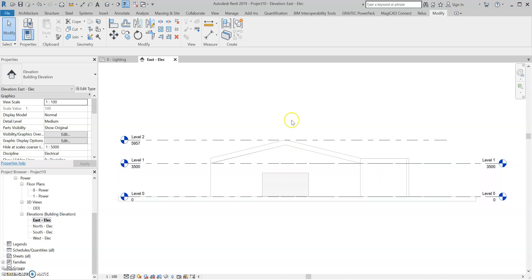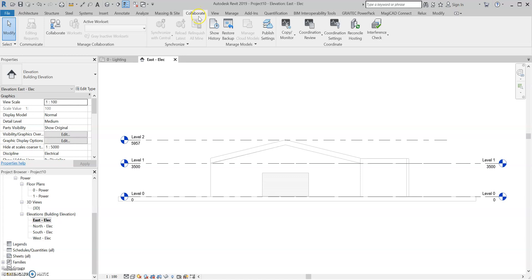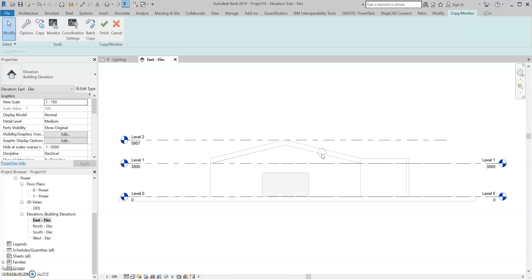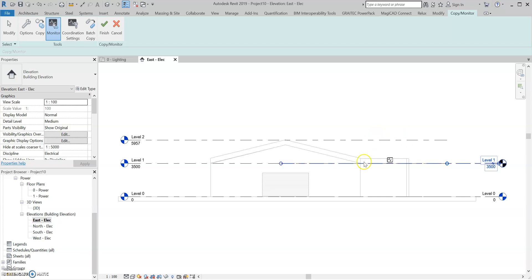Now I'm going to monitor these levels, just in case the architect moves his — I want to be notified of a coordination alert. So I'm going to go to Collaborate, Copy Monitor, and Select Link. I'm going to select the link, go over to Monitor, and select the electrical level first and then the architect level second. You'll notice you get this little heartbeat sign, and that is exactly what you're looking for. If it doesn't come up with that, you might not have done it right, so just go through the process again.